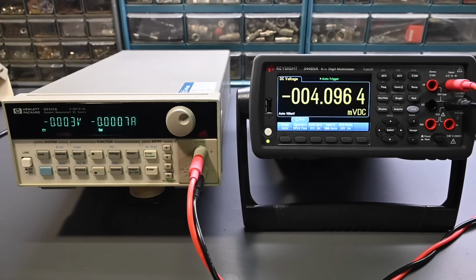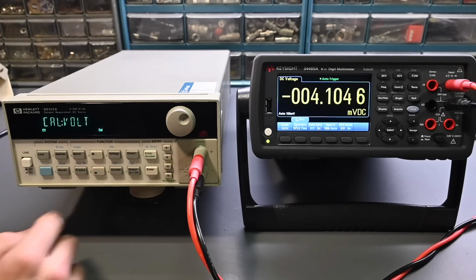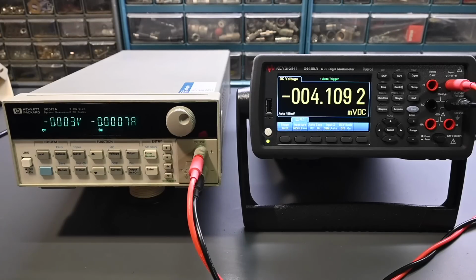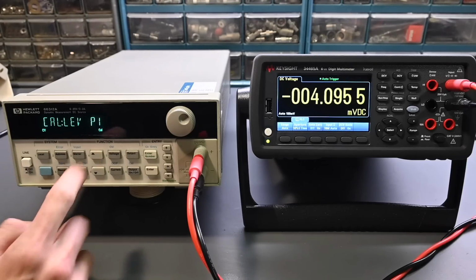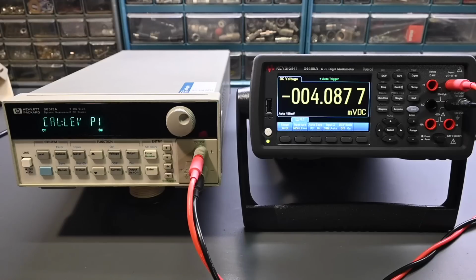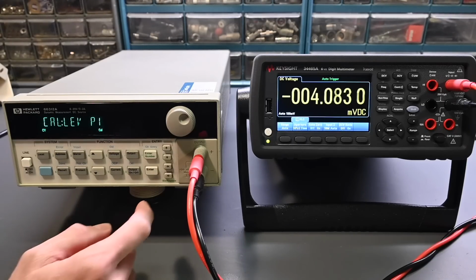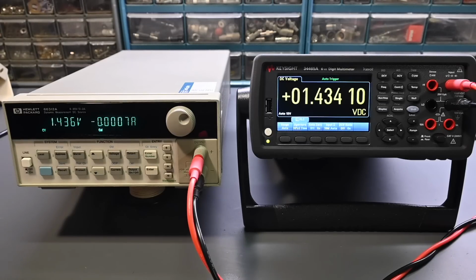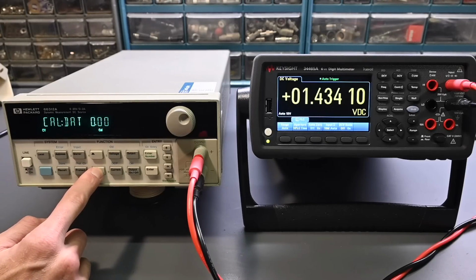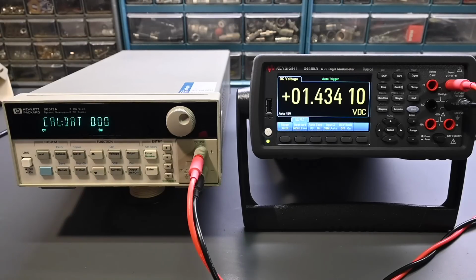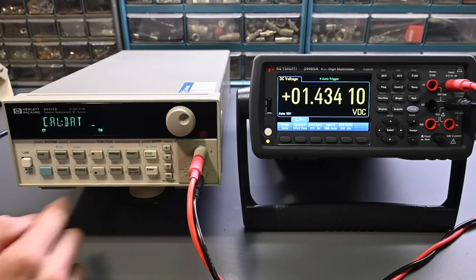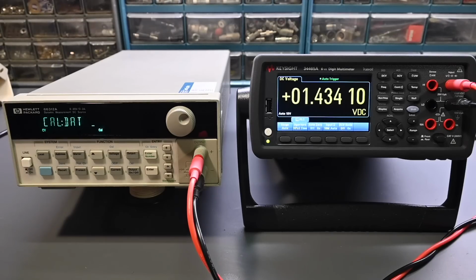It says to press shift cal, so we'll do that, shift and cal. Scroll to cal volt. Right there, press enter. It says press shift cal, scroll to cal level, right there, and it says it should be on cal level P1, which it is. Press enter to select the first calibration point. Press shift cal, scroll to cal data, there. And it says press enter number, and enter the voltage value displayed on the digital multimeter. So we do have a nice stable reading over there.